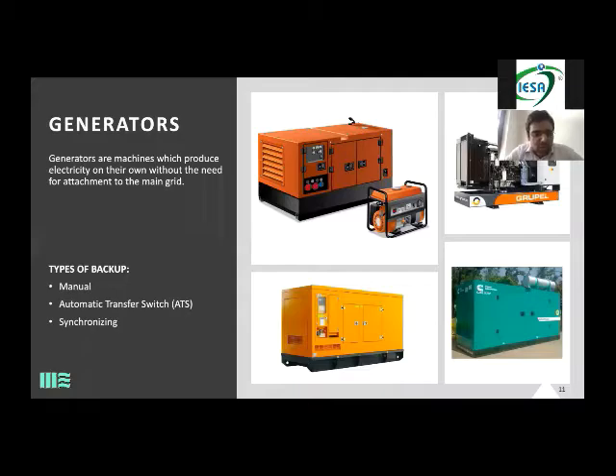So basically, if you're buying a genset, it is compatible to sync. It is a synchronization panel which is already available inside the genset. Normally a genset comes with a panel, so this is a sync panel. There are certain gensets where the sync, in Cummins or all those gensets, is only possible at 500 kVA and above.